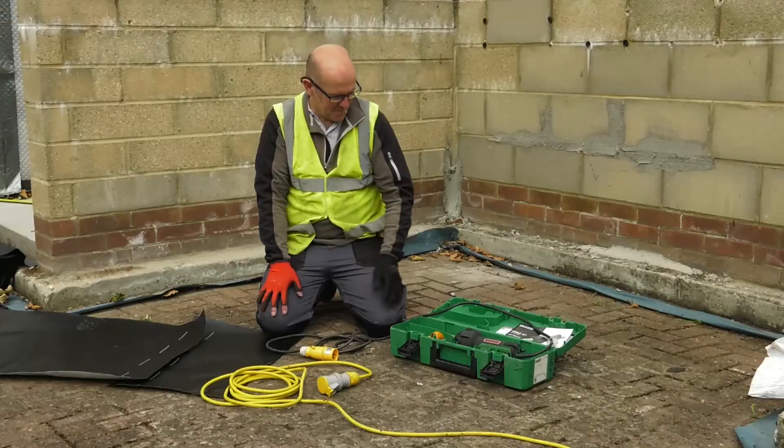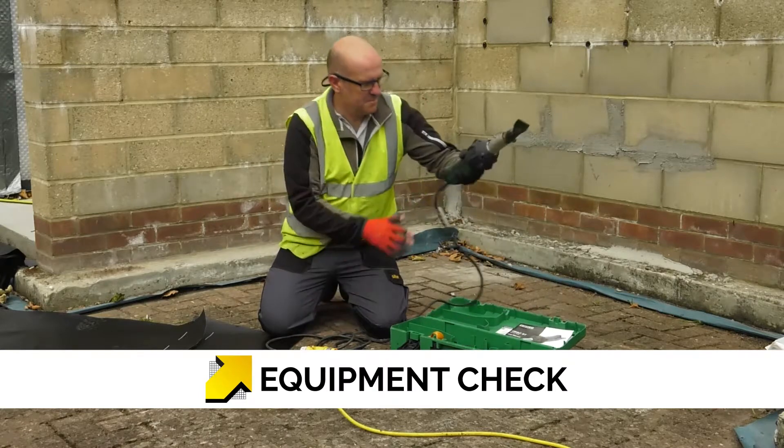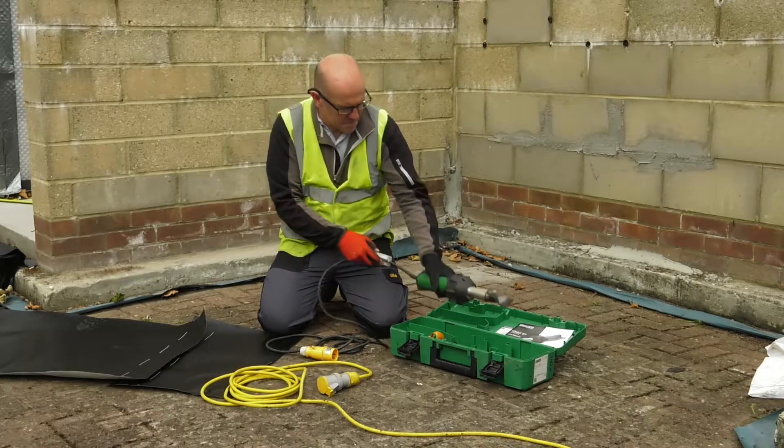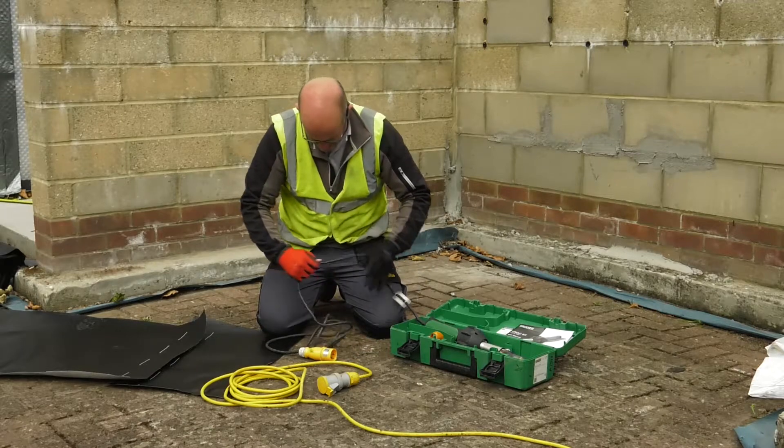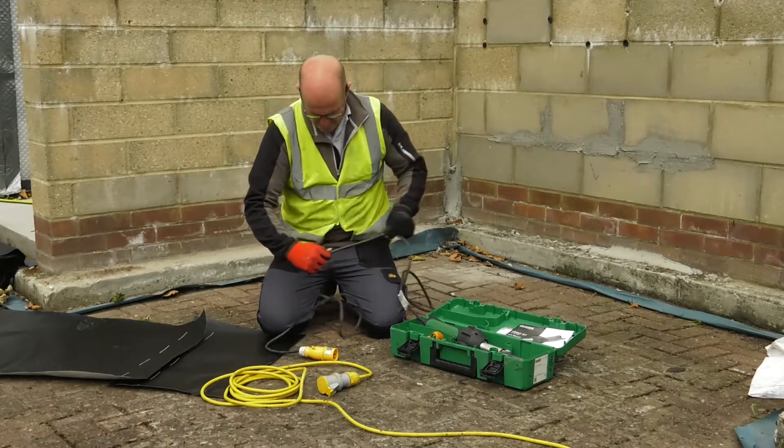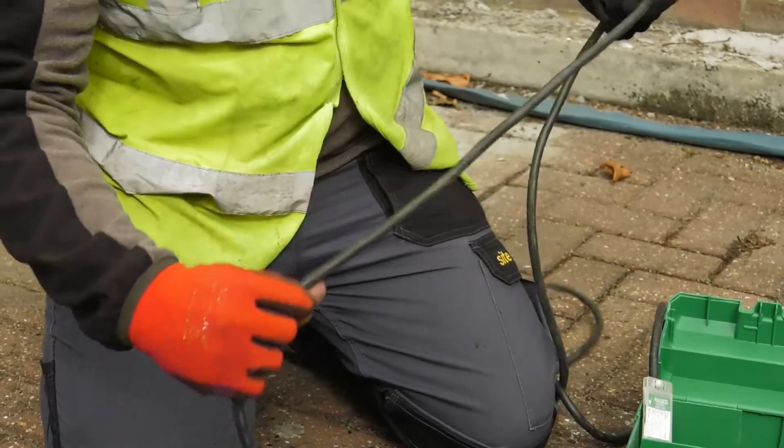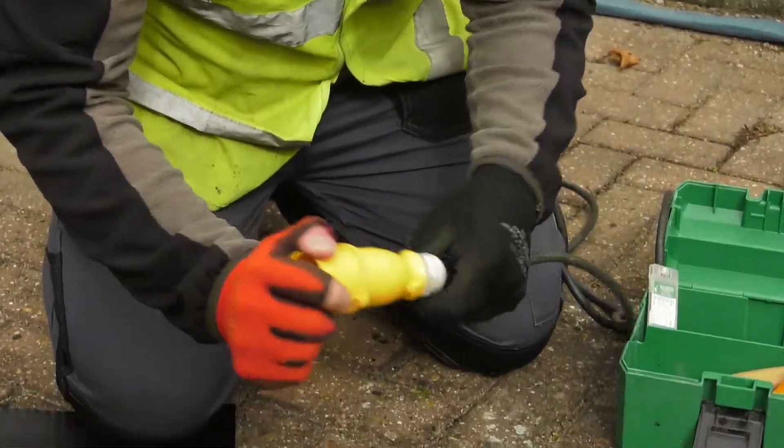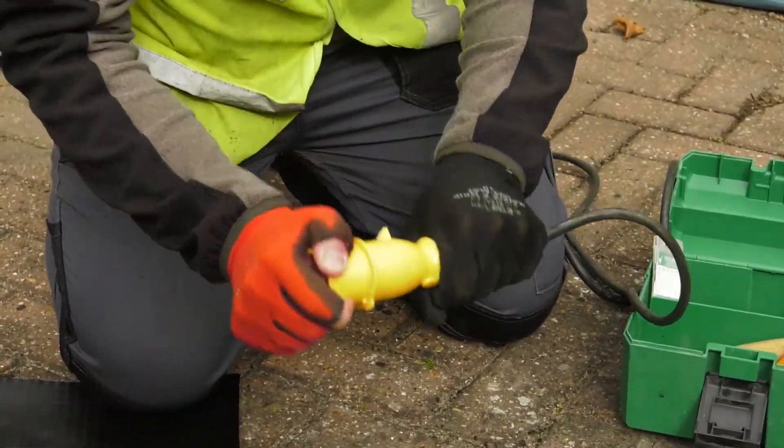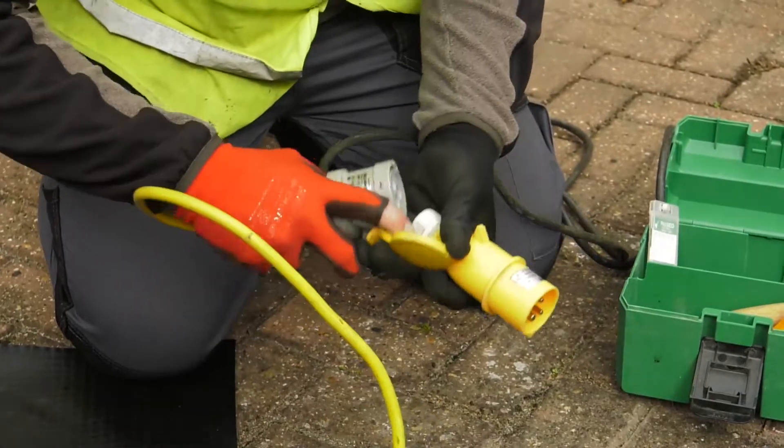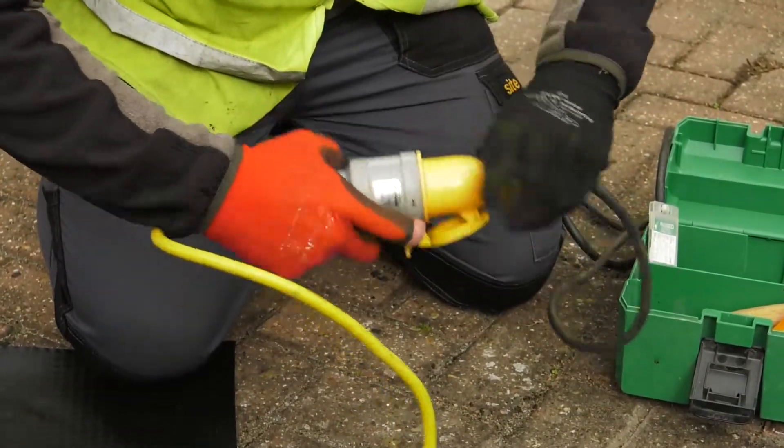It is essential to check all tools before they are used. Look at the leads, plugs and connections, and check the PAT testing is in order and up to date. Visually inspect all leads for any breaks or damage. Also check the sockets are in place and are in good order and will connect properly.